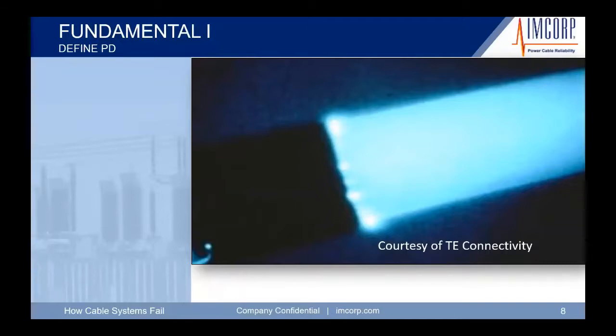So I always ask people, why do you do a cutback when you're installing a termination, connecting it to a piece of equipment, or extending a cable with a splice? What happens is you have to create some distance between the inner conductor and the outer conductor. If you had a piece of cable and you just took enough material to put a lug on it and you installed it and energized it, you'd have an immediate flashover. So here you have to cut back anywhere from 5.5 inches to about 8 inches. Rule of thumb back in the day was for every 1 kV of cable, you had to do a cutback of 1 inch. Today, technology has changed quite a bit, so those cutbacks are a lot shorter to do.